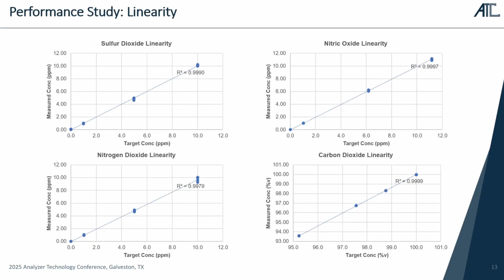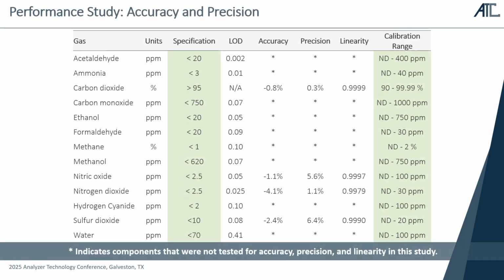Next, for linearity, you can see here across the specified range of 0 to 10 ppm for each of the impurities, we showed good linearity. Linearity is always important to show the transient property. It allows us to have faith in our calibration, that we can hit the points as the concentration is changing over time. And here's a summary of everything. You'll note the starred components, those were not tested during this study, but overall the study verified that an FTIR is a viable solution for measuring these with high accuracy and precision.